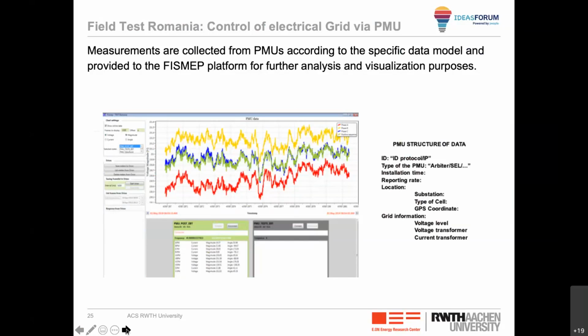In this study, PMUs are installed in a few nodes of the high voltage grid, monitoring and connected via current and voltage instrument transformers from the substation of the power grid. Each PMU is identified by an ID and its position, which is taken via GPS. For this specific test case, we took 5 PMUs, and the data are gathered and visualized by the web cloud.